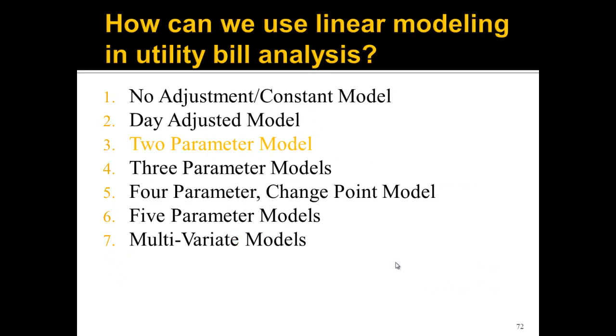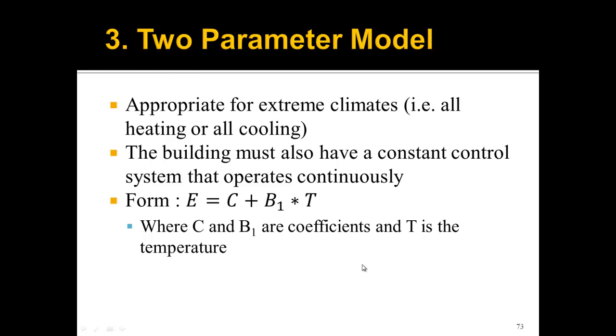Now let's look at the two parameter model. The two parameter model is appropriate for extreme climates, so if you have all heating or all cooling. The building must also have a constant control system that operates continuously. It shouldn't be shut off at night or during some months of the year. It should have continuous control. This is very specific, not generalized at all. So that's one drawback of this model.